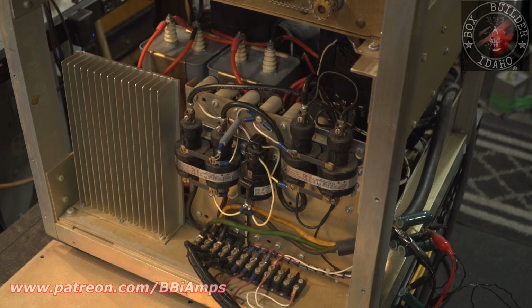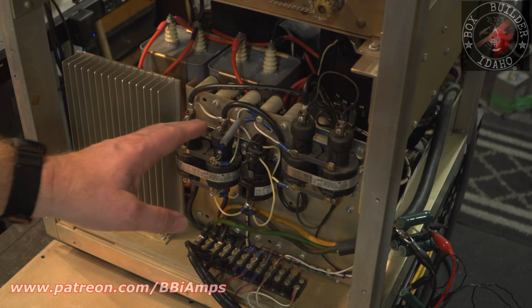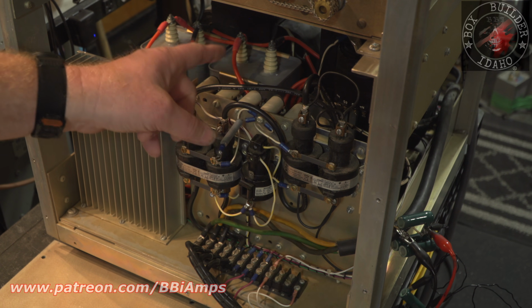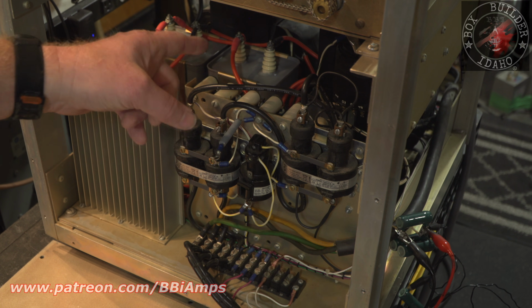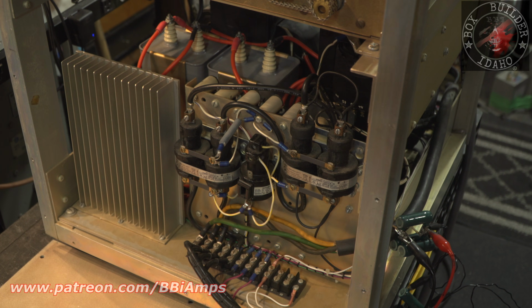But then that doesn't address our soft start issue. I like to have at least 1 or 2 seconds where that resistor is taking 100% of the load and those caps are slowly getting filled up. That incredibly increases the lifetime of the capacitor.